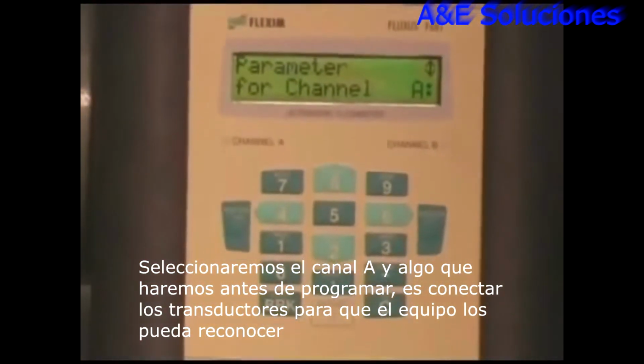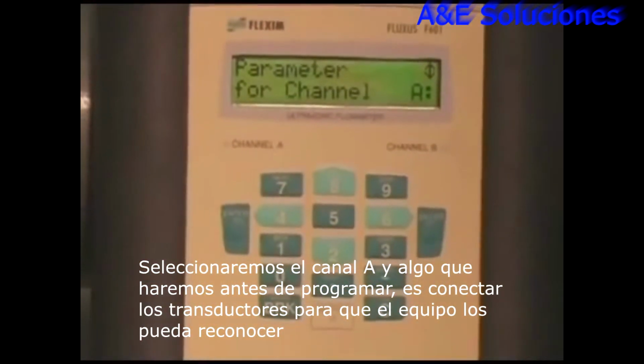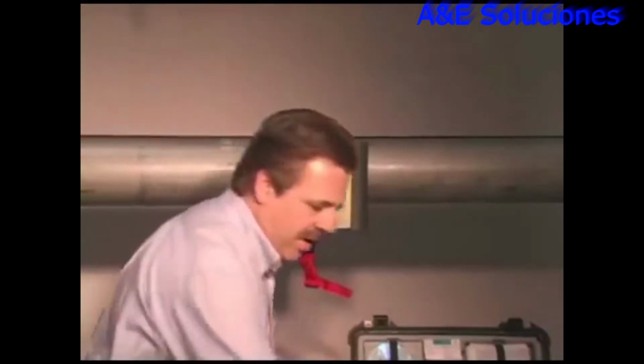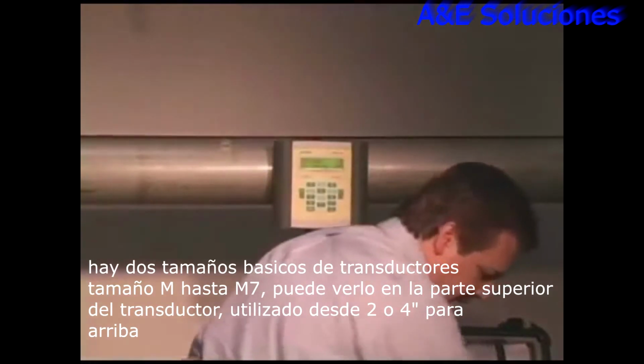Okay, so we're going to choose channel A here, and one of the things we also want to do before we start the programming is connect up our transducer, because the meter needs to recognize the transducer and know which transducer we're doing our measurement with.